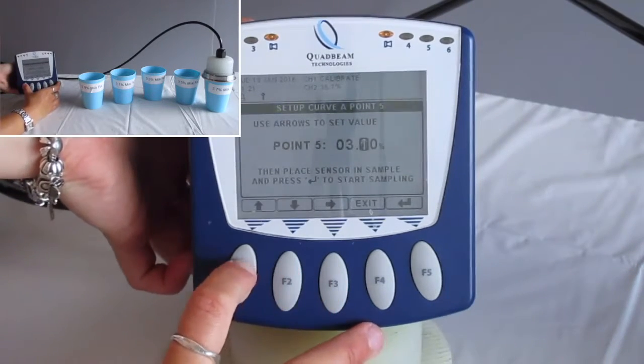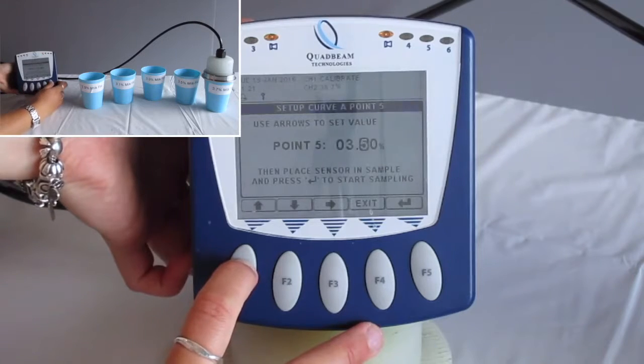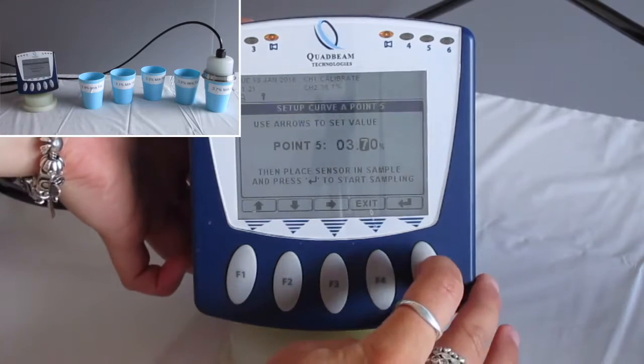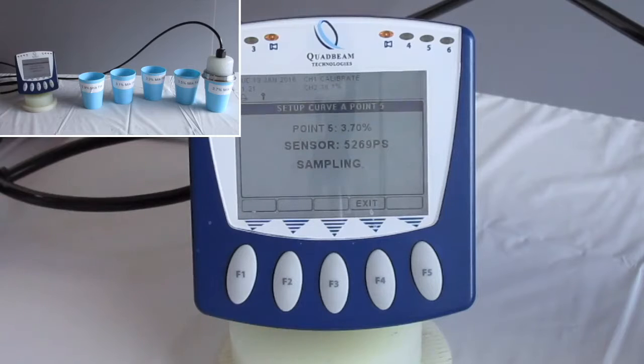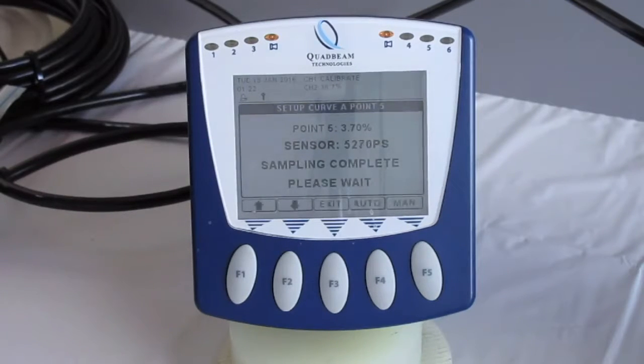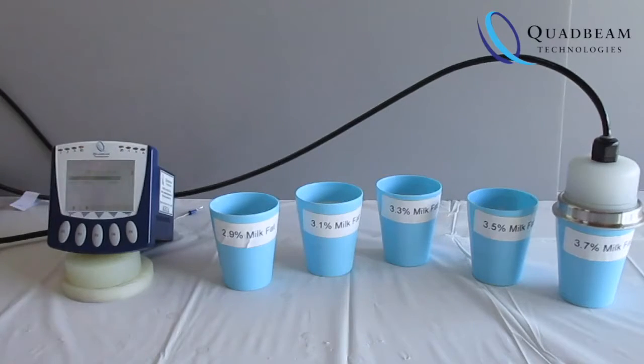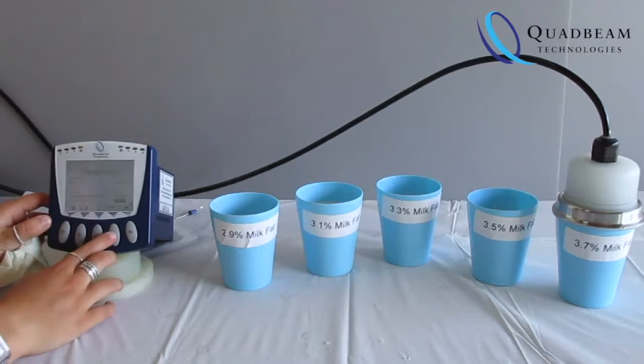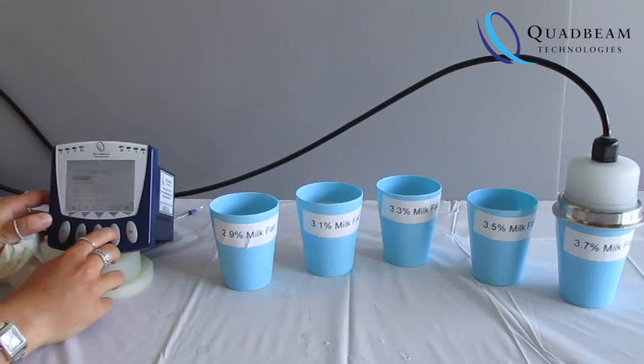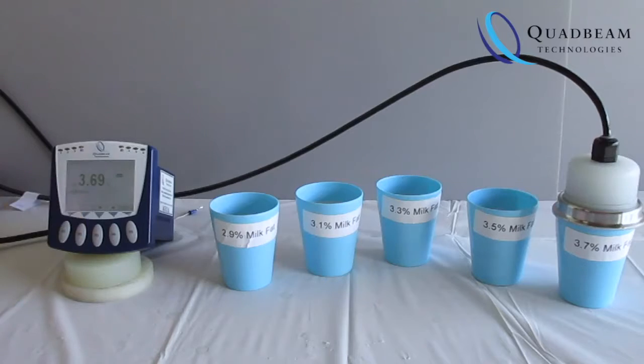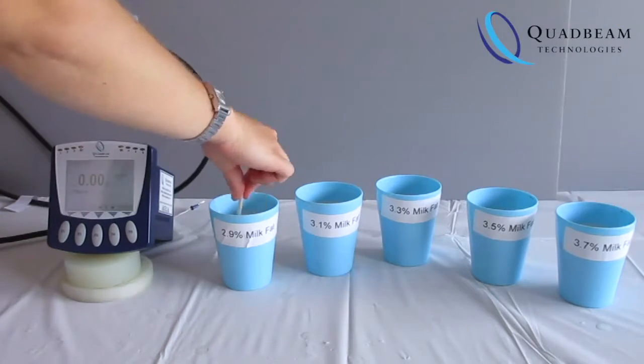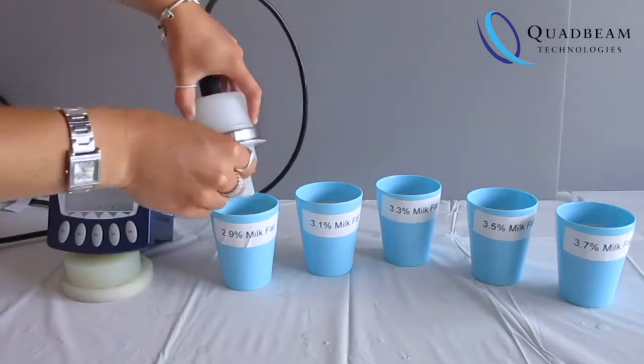It's likely you'll need to do some fine tuning once installed, as the reflection of the pipe is going to be different from the cups that you've used during the setup process. Simply take a sample from the line, at the same time reading the output from the Quadbeam. You can adjust the zero and span through the calibration section of the menu. This is different to the channel setup that we're using at the moment.